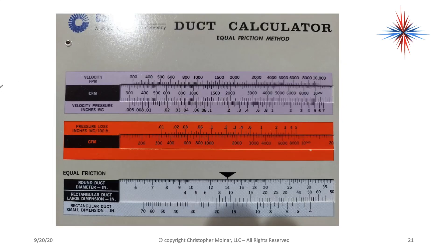Another type of ductulator — again you have your 14-inch round. If you have rectangular duct, you can also use the slide rule with your large dimension and small dimension. For example, a 20 by 12 duct equals a 14-inch round. Based on whatever static pressure you use — at 0.08 it's about 900 CFM, at 0.1 it's a little over 1,000 CFM. There's a slight difference between different ductulators, but it still gets the point across.